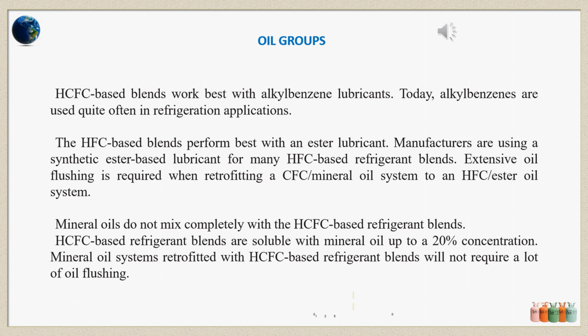Mineral oils do not mix completely with the HCFC-based refrigerant blends. HCFC-based refrigerant blends are soluble with mineral oil up to a 20% concentration. Mineral oil systems retrofitted with HCFC-based refrigerant blends will not require a lot of oil flushing.